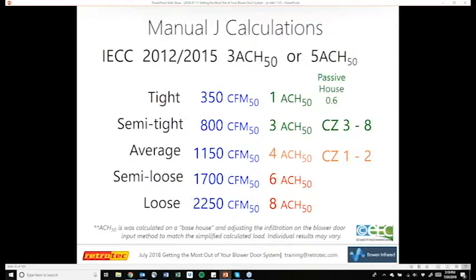If someone just assumes that it's tight, well, as far as concerned, that's 1 ACH 50. That's really tight. And passive house is 0.6, so that's getting in that neighborhood. And then loose is 8 ACH 50. Some existing homes, older homes might even be more loose than that. And so that's when it's going to be really important to actually enter in that correct number from a blower door test.